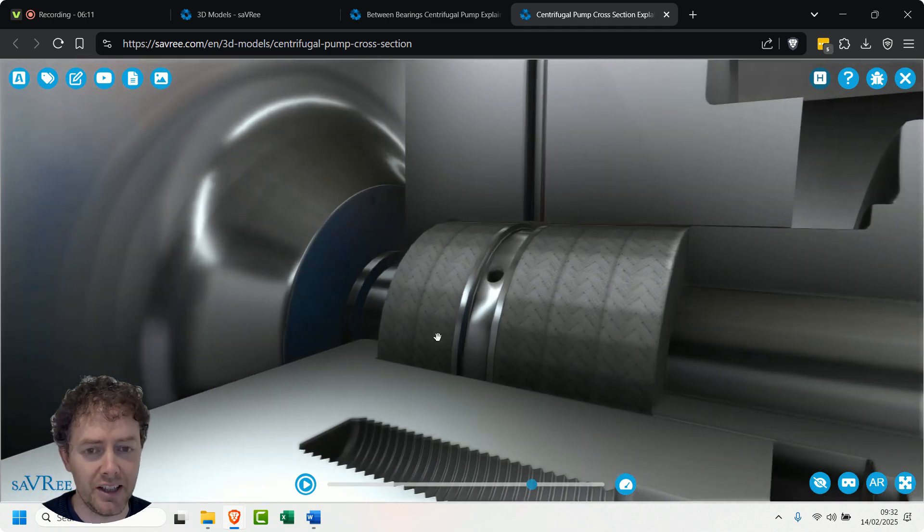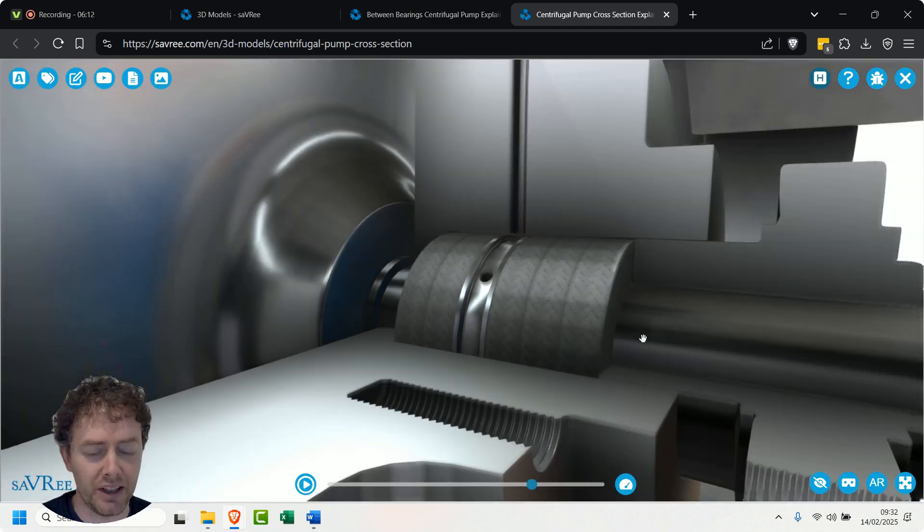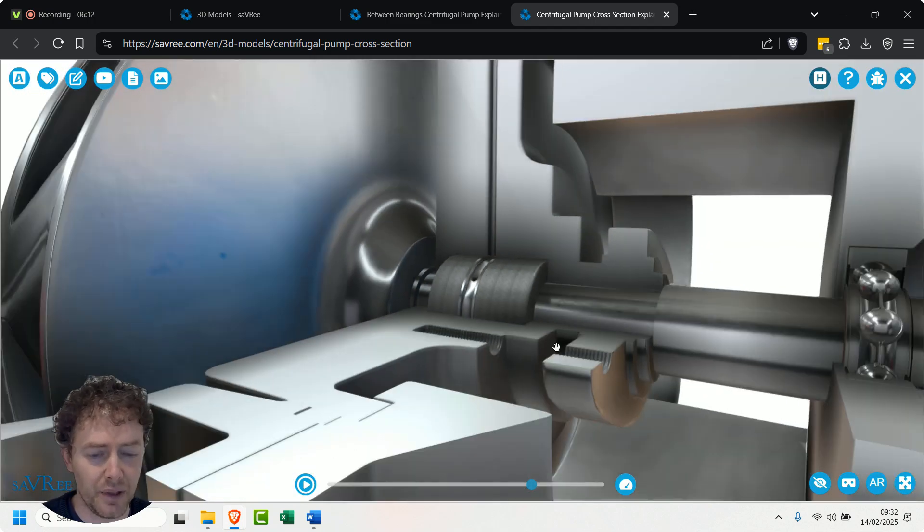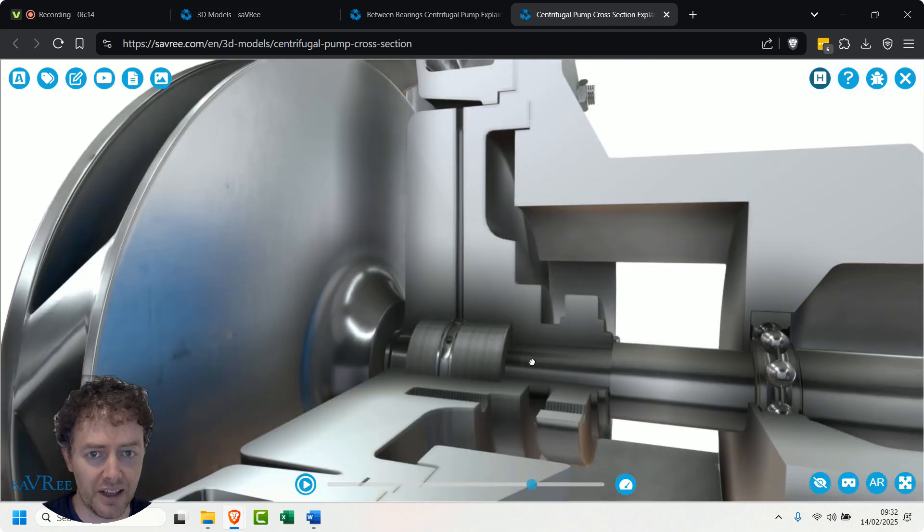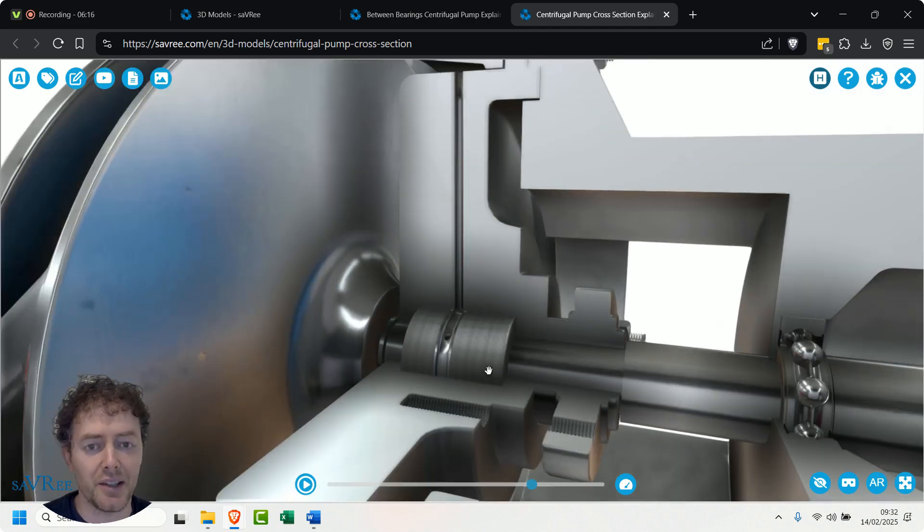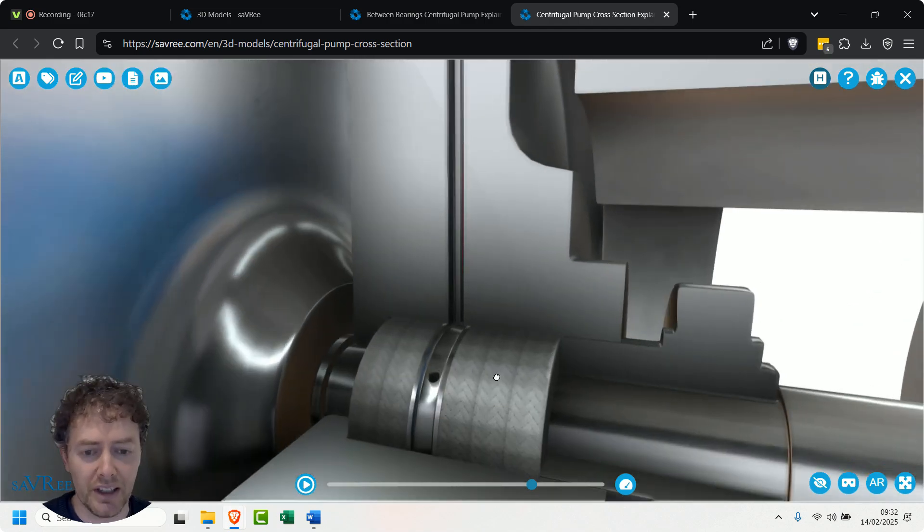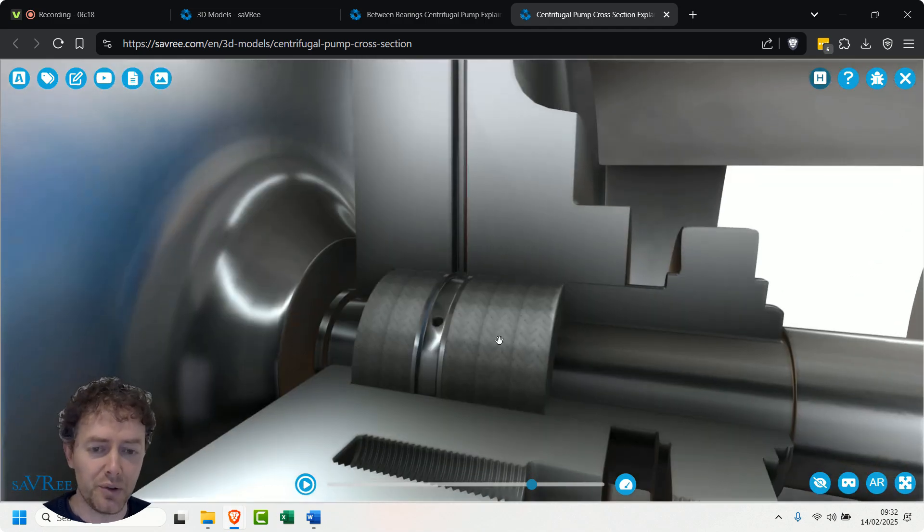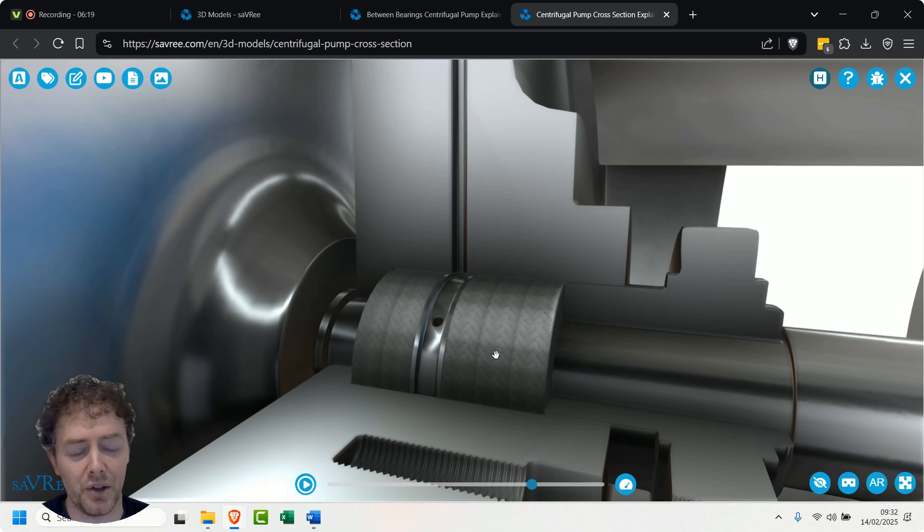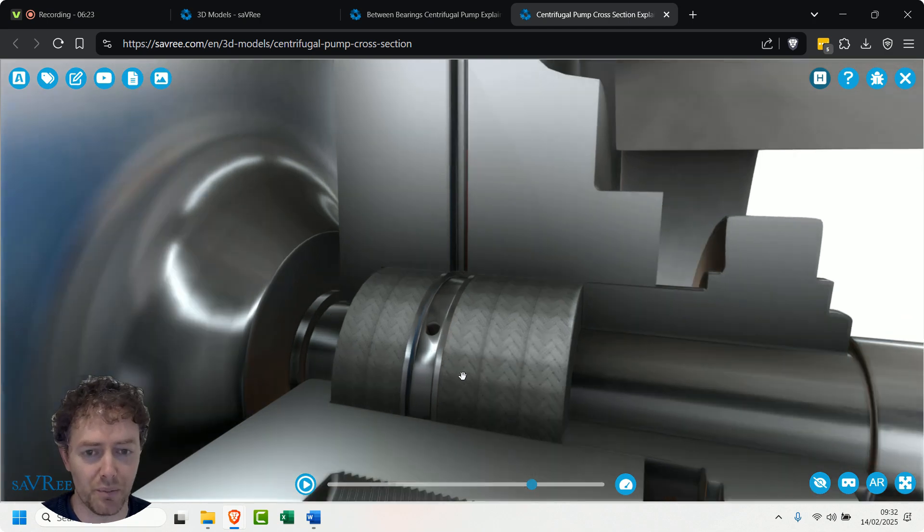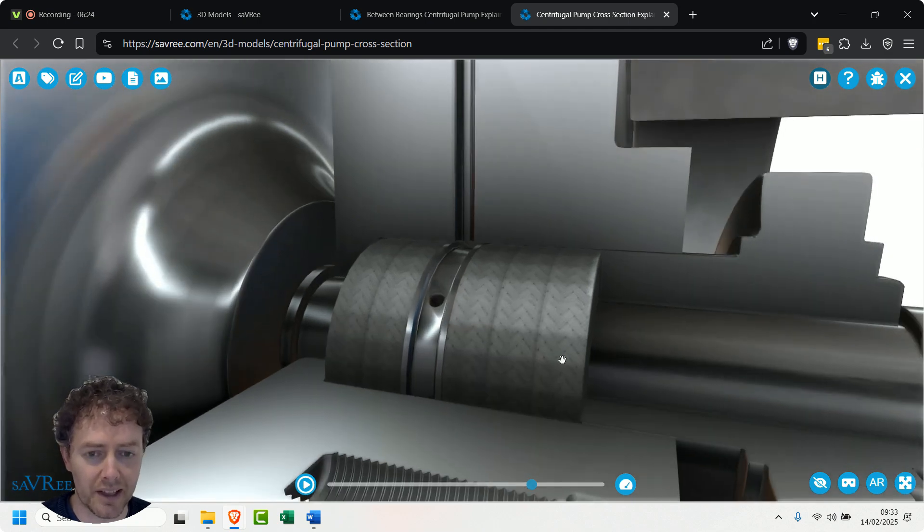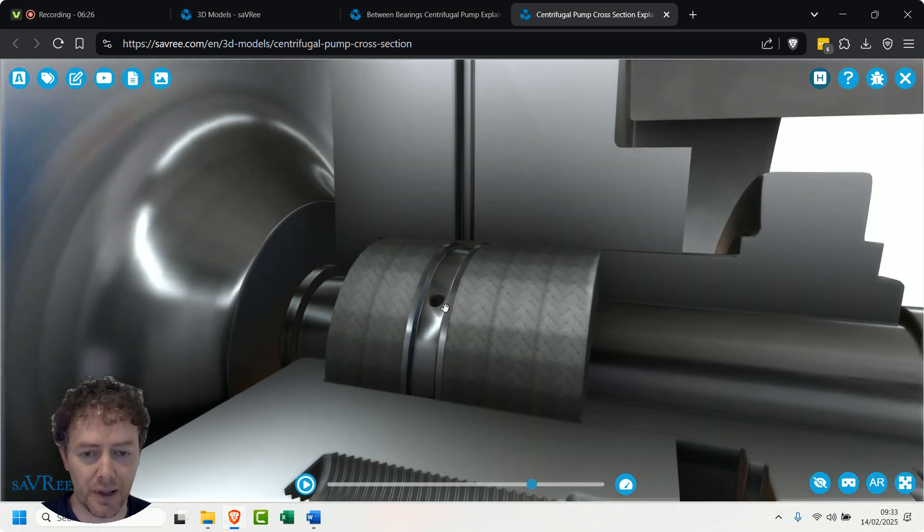You can see the shaft penetrates through here, so we're not going to get any leaking coming through here and then being discharged into the surrounding area - that's the purpose of it. If we don't use packing, what we're going to use is a mechanical seal. Mechanical seals cost a bit more, so people tend to use packing. There are some other benefits with mechanical seals, but generally you'll see packing quite often because it's cheap and it's cheerful.